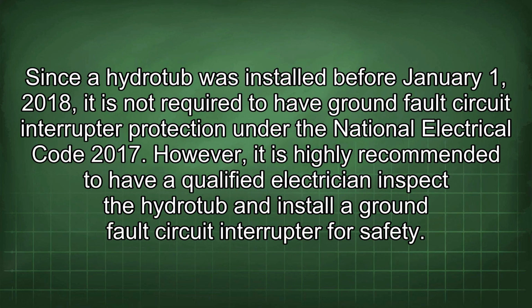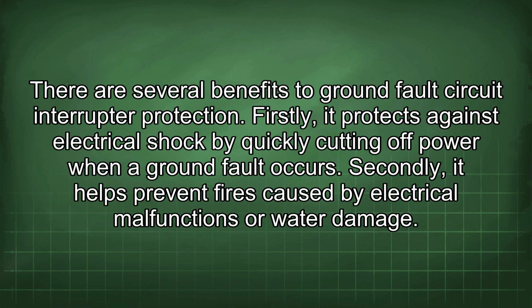Since a hydrotub was installed before January 1, 2018, it is not required to have ground fault circuit interrupter protection under the National Electrical Code 2017. However, it is highly recommended to have a qualified electrician inspect the hydrotub and install a ground fault circuit interrupter for safety. There are several benefits to ground fault circuit interrupter protection.